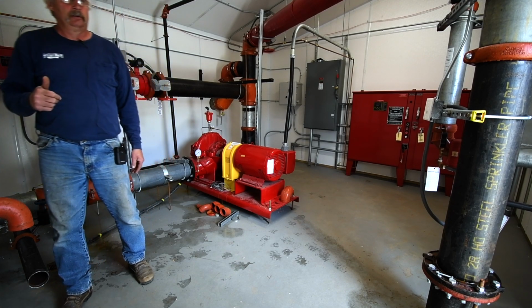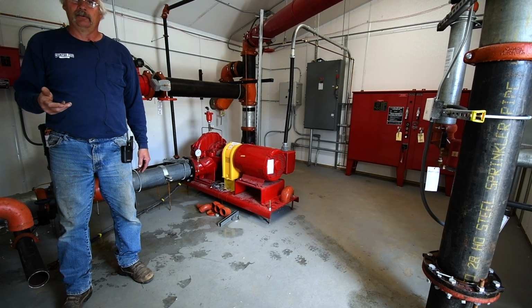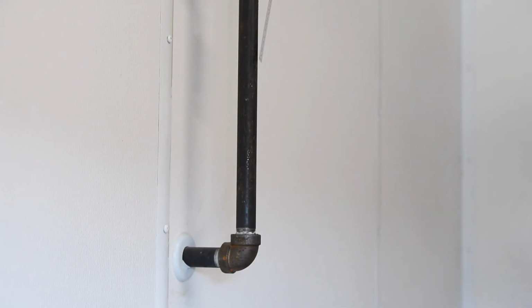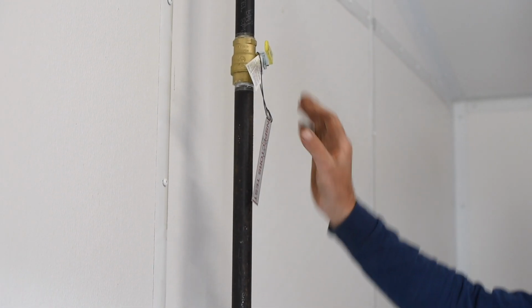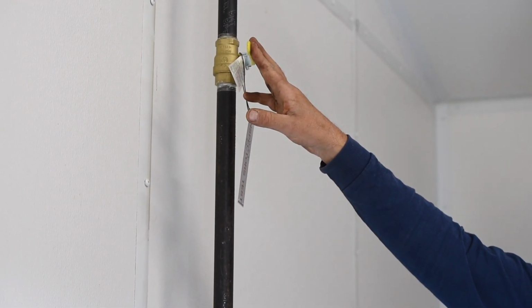There's 1A, which you turn the control valve off after, if you have a head go off or something, a fire or freeze up, whatever, loss of heat. Step 2 would be open main drain B. Step 3 would be the inspector's test again, which would be labeled C. So this is normally closed. So if you want to drain the water out, open it up.